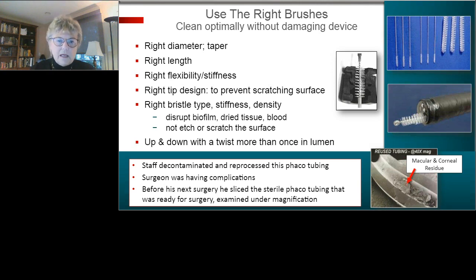that can cause devastating effects within the eye. Staff decontaminated and reprocessed this phaco tubing on the right, and they found that the surgeon was actually upset. He was having problems with damaged eyes with TASS as well as non-infectious endophthalmitis. And they kept saying, no, we're perfect, doing everything right. And he took the tube, as it was going into the patient, and he sliced it open and found these particular chemical residues, which turned out to be causing the problem.